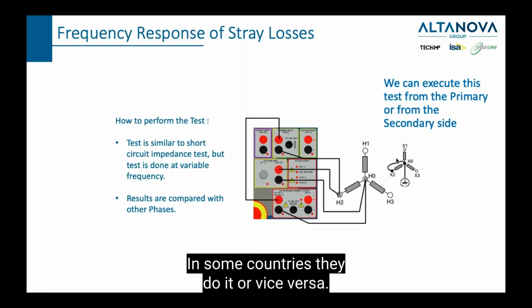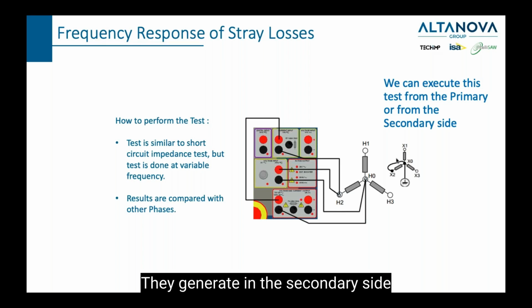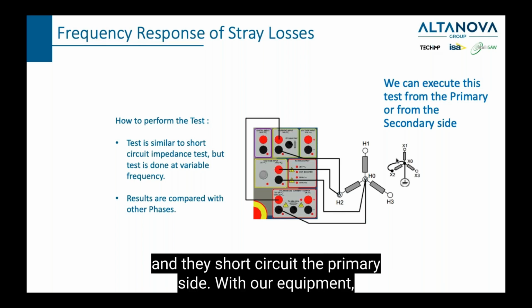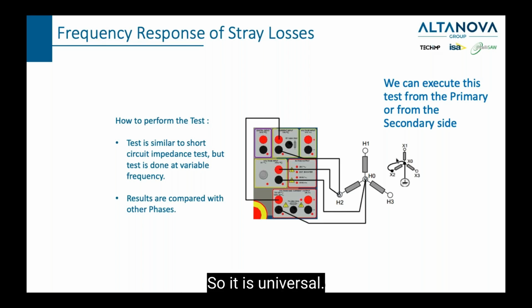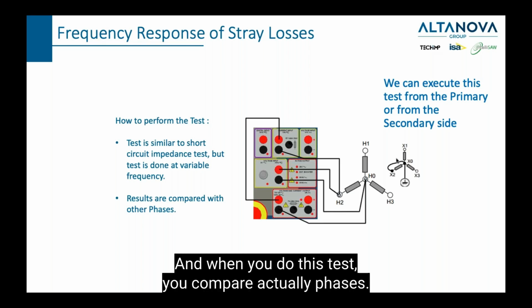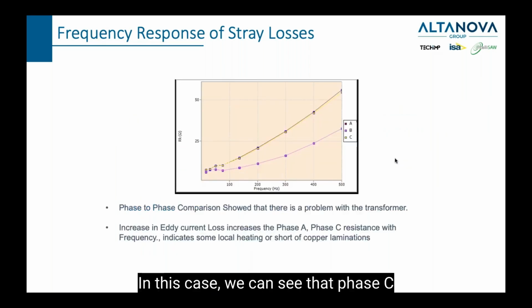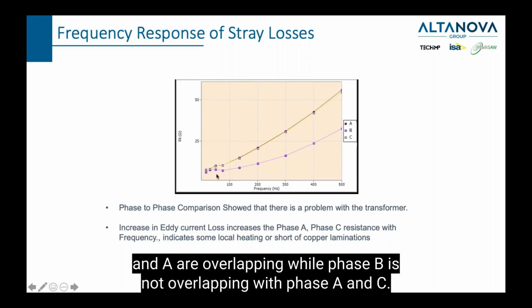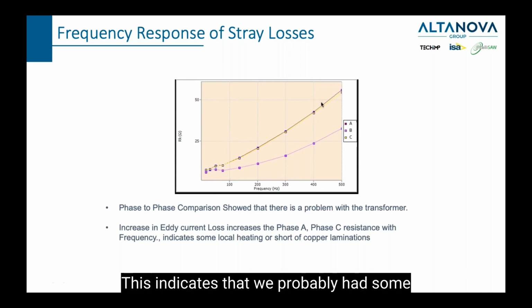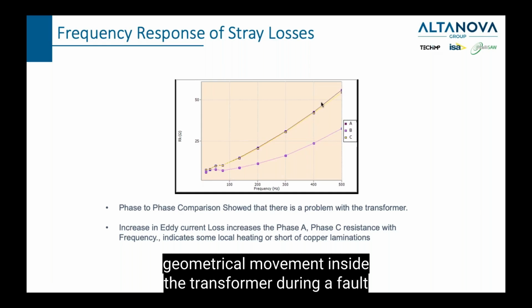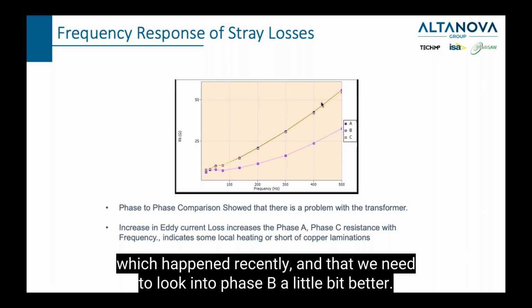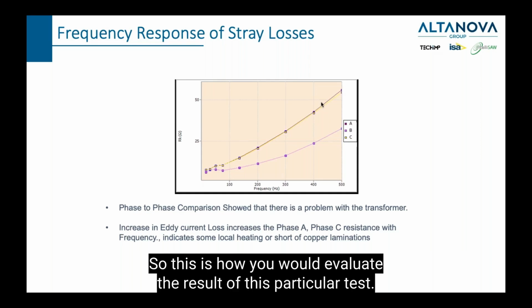In some countries, they do it vice versa. They generate on the secondary side and they short circuit the primary side. With our equipment, you can do it both ways, so it is universal. And when you do this test, you actually compare phases. In this case, we can see that phases C and A are overlapping, while phase B is not overlapping with phases A and C. This indicates that we probably had some geometrical movement inside the transformer during a fault which happened recently, and that we need to look into phase B a little bit better. So this is how you would evaluate the result of this particular test.